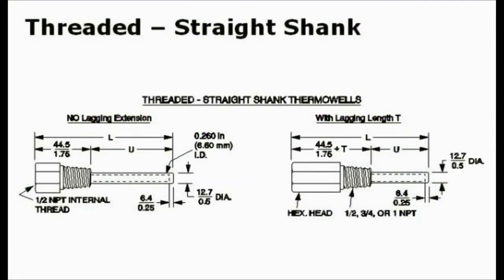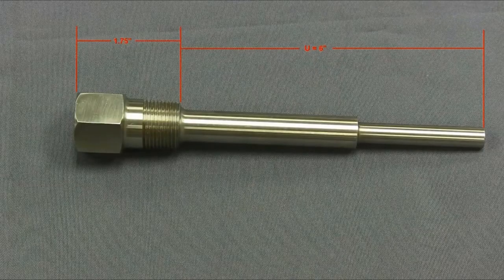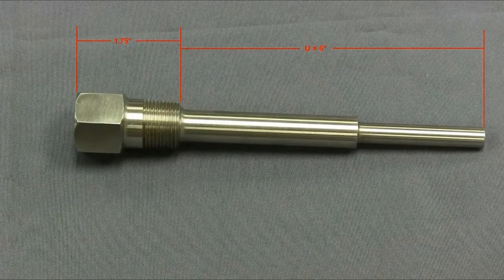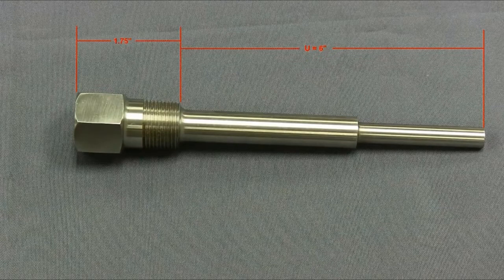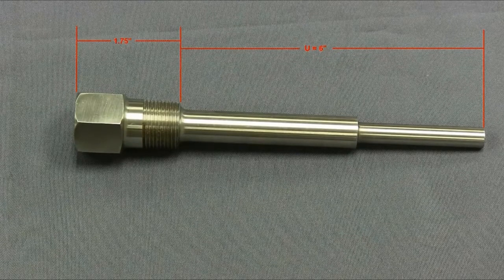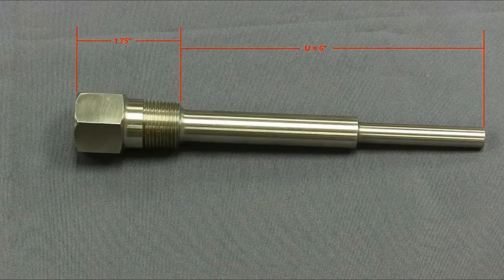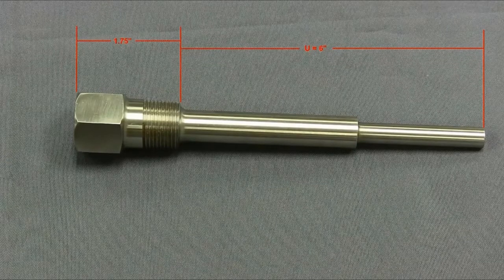Let's begin by reviewing exactly where the thermowell U insertion length and the T lagging length are located and measured on the thermowell. The U insertion length is measured from the tip of the thermowell to where the threads start. This measurement shows the well has a U dimension of 6 inches.